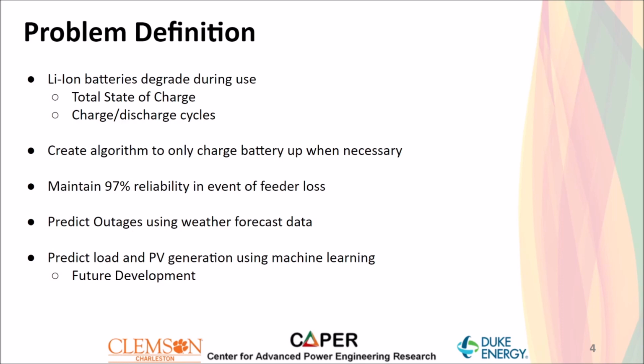It'll maintain a low average while still employing the peak shaving component to make best use of cheaper generation and off-peak hours. But we're also maintaining a goal of 97% reliability in the event of a feeder loss. We can predict outages using weather forecast data, charge the battery ahead of time, and then deploy it in an islanding mode while repairs are underway on the primary feeder to keep a local area of load, keep the lights on for those customers rather than a complete outage.